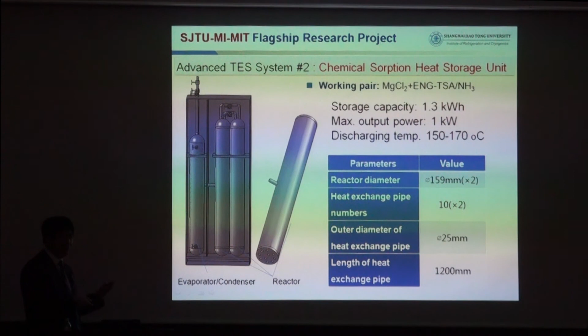As I mentioned, Shanghai Jiao Tong commercialized this kind of air source heat pump water heating system in 2003. We then received a request about whether the tank could be reduced. Normally a family tank is only 150 liters; in the Japanese market for CO2 systems it's 300 liters, the difference being that we take showers while the Japanese take full baths. So we are considering whether we could reduce it to 50 or 80 liters so it won't occupy as much ground space, and we're looking at whether it's possible to use three-phase sorption for this.